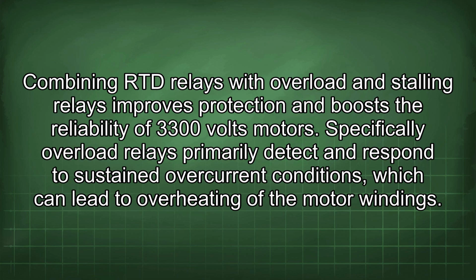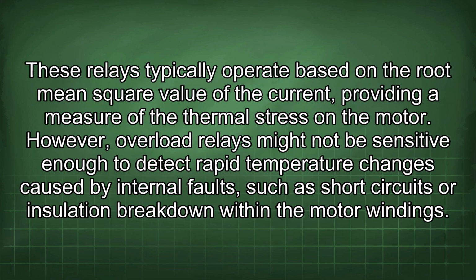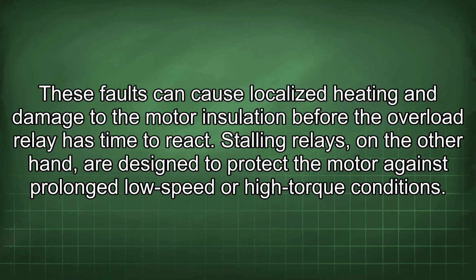Combining RTD relays with overload and stalling relays improves protection and boosts the reliability of 3,300 volts motors. Specifically, overload relays primarily detect and respond to sustained overcurrent conditions, which can lead to overheating of the motor windings. These relays typically operate based on the root mean square value of the current, providing a measure of the thermal stress on the motor. However, overload relays might not be sensitive enough to detect rapid temperature changes caused by internal faults, such as short circuits or insulation breakdown within the motor windings. These faults can cause localized heating and damage to the motor insulation before the overload relay has time to react.